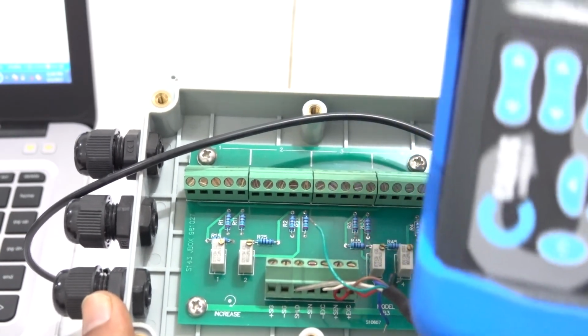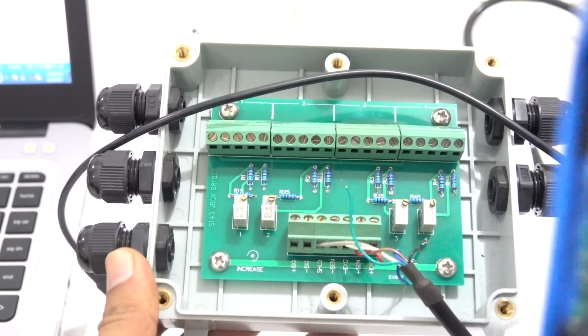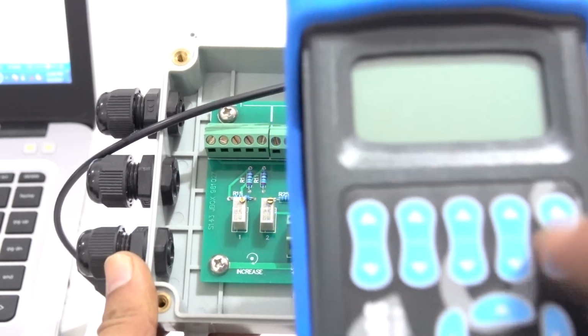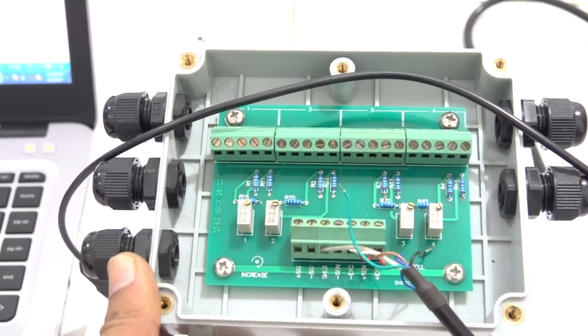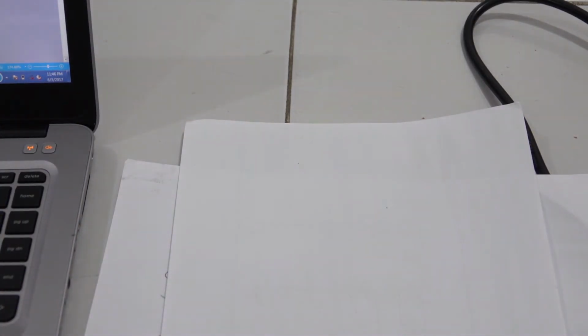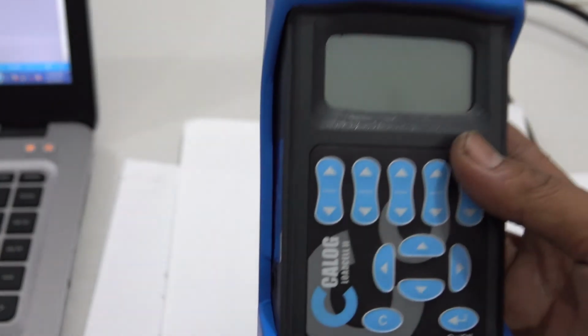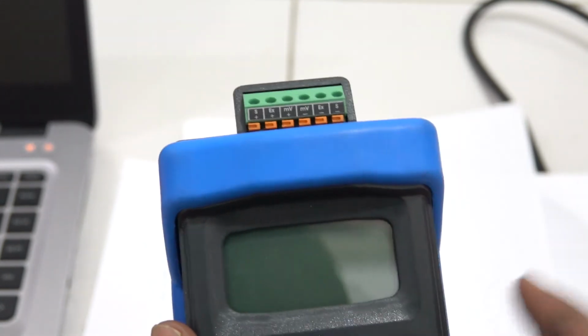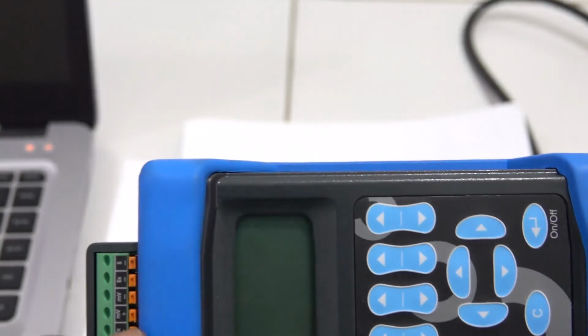You don't connect the load cell to the junction box, but you connect this equipment to the junction box, and you make a simple calculation. You can search on the internet how to calculate it and generate the millivolts sourced by this equipment to the junction box, to be read by the load cell indicators. And then you can do a verification, maybe by actual load, to see how it mechanically behaves, because although you do this electronic calibration, it doesn't mean it will represent the mechanical behavior of the system. There is no correlation at all, so you have to be careful to do that.